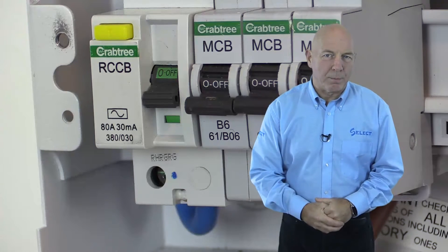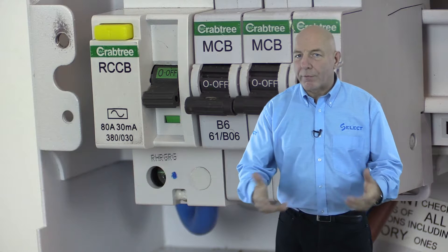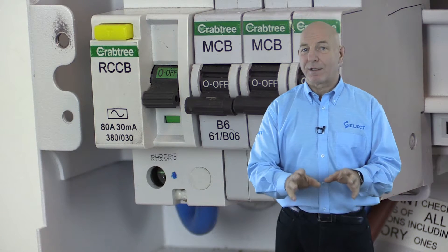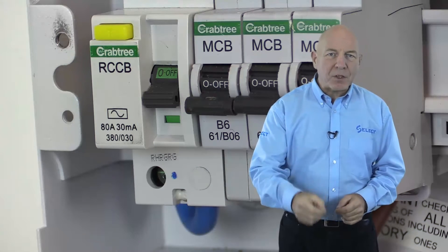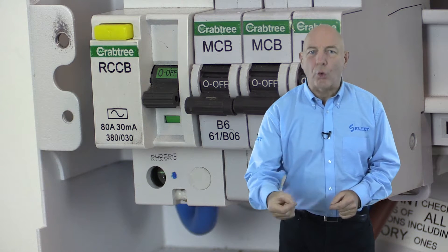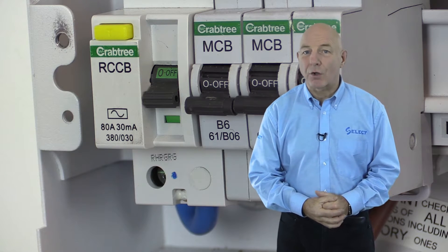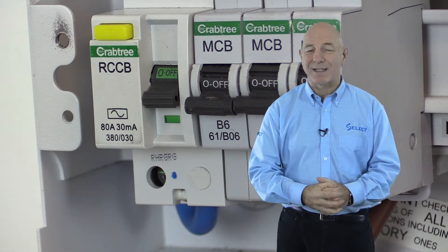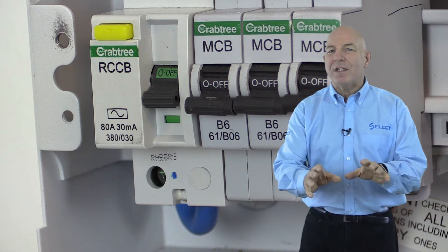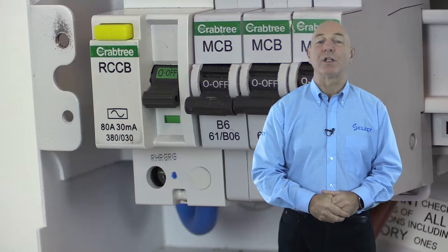Maximum earth fault loop impedance values: fuses and circuit breakers, overcurrent protective devices, have different operating characteristics depending on the product standard and type. To ensure sufficient fault current is produced during a fault to cause operation, it's important that the earth fault loop impedance does not exceed the maximum impedance value necessary to achieve this. These maximum earth fault loop impedance ZS values are provided in Chapter 41 of BS 7671 in Tables 41.2, 41.3, and 41.4. This is Table 41.3.